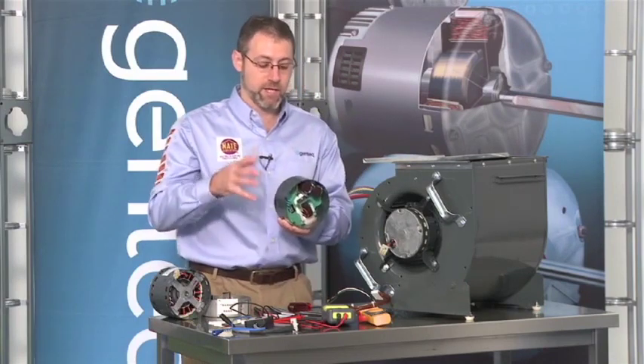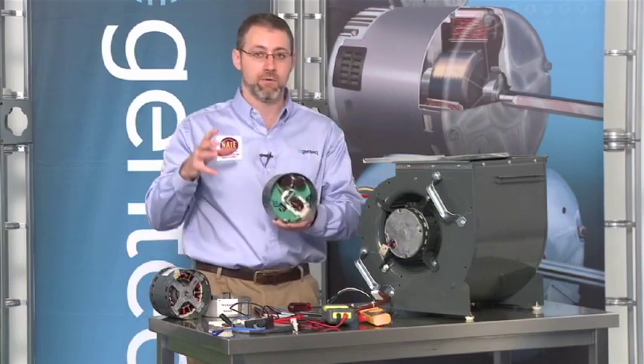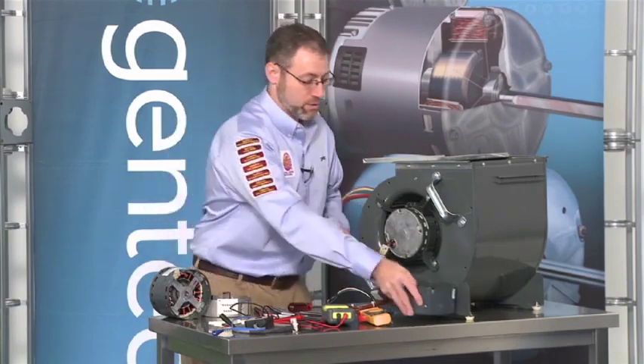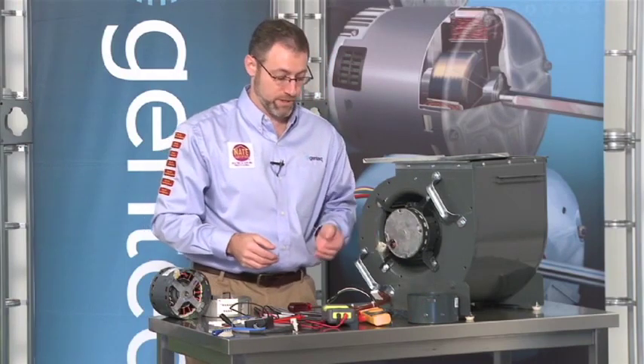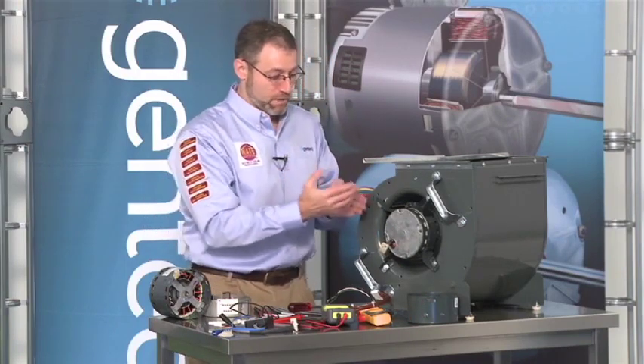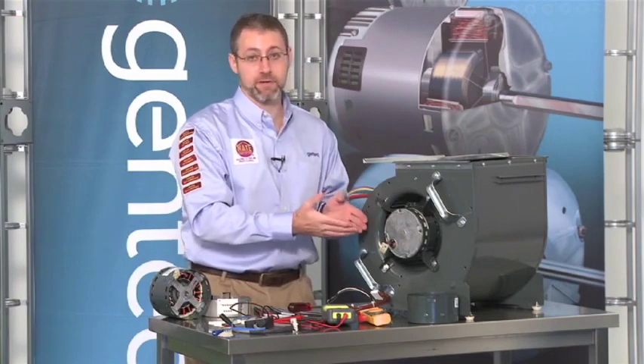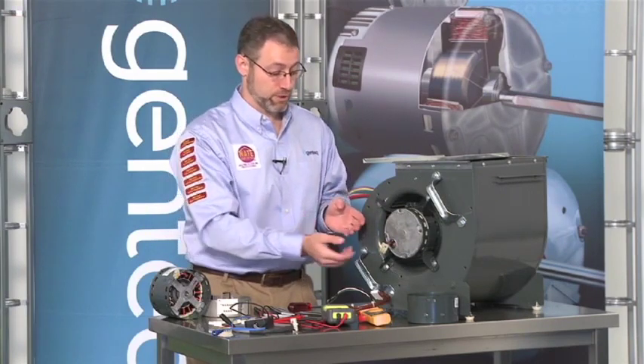So with the TechMate, we've diagnosed that the motor does not run. We've diagnosed that this control is failed. So we're going to put that off to the side and now we're going to diagnose whether the motor is failed or not. And really, what you have right here is a three phase motor, no different than any other three phase motor.